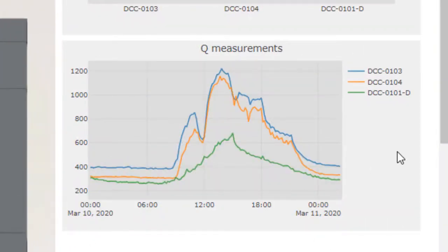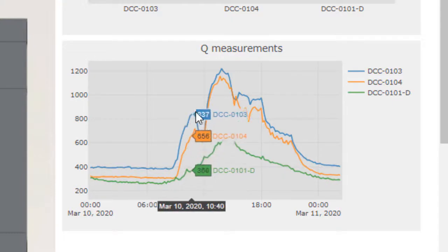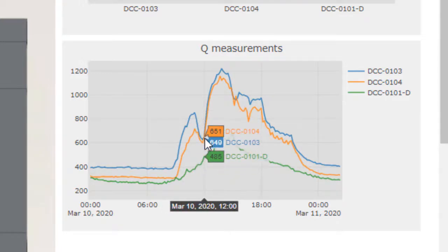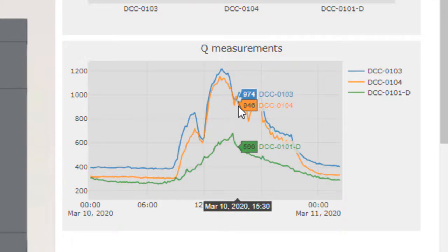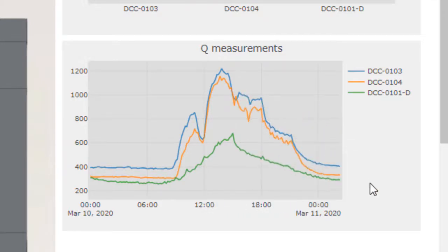If we zoom in, we observe a quite interesting pattern that happens daily. CO2 starting to increase at 8:30, then drops at 11 a.m., which may suggest people leaving the room, and CO2 levels increasing again from 12 p.m. to 2 p.m. and fall gradually until midnight. These patterns that are different between classrooms can be used to predict occupancy and even estimate the number of occupants with proper machine learning algorithms.